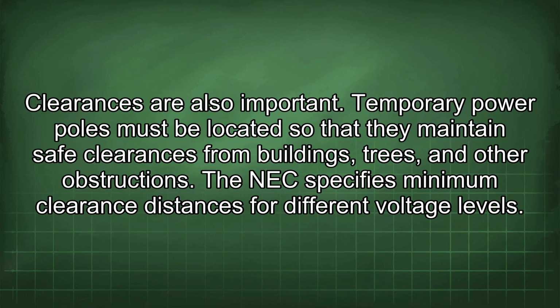Clearances are also important. Temporary power poles must be located so that they maintain safe clearances from buildings, trees, and other obstructions. The NEC specifies minimum clearance distances for different voltage levels.